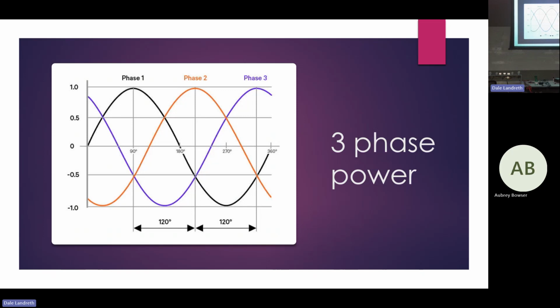Exactly. So a contactor like this, can you replace the contacts on these? Yes. Are contacts cheap? They're not. So if we allowed this to continue happening, the contacts will pit. And if we give enough pitting in the contacts, what's going to happen to the stator, the motor? It's going to cause excessive current, or more current, somewhat, whatever it may be. We may weld the contactor.